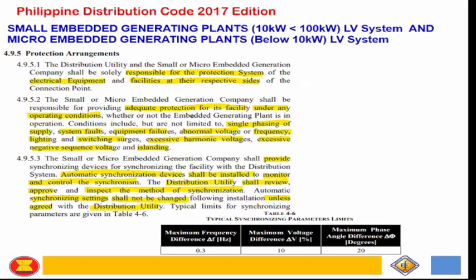But for the small and micro, which are on the low voltage side and include solar panels, the provision is that they are responsible for protection of their electrical equipment and facilities. It is the same as the provision for the higher generating plants, but with adequate protection for each facility under the operating condition, including single phasing, which is really emphasized.